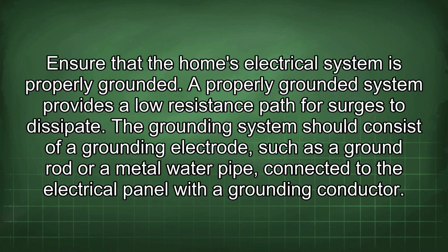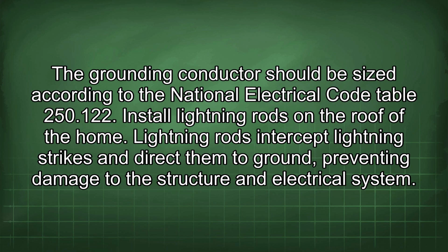Ensure that the home's electrical system is properly grounded. A properly grounded system provides a low resistance path for surges to dissipate. The grounding system should consist of a grounding electrode, such as a ground rod or a metal water pipe, connected to the electrical panel with a grounding conductor. The grounding conductor should be sized according to the National Electrical Code Table 250.122.